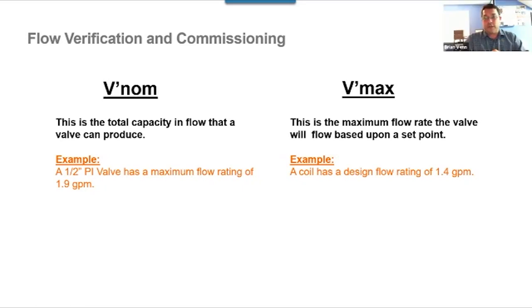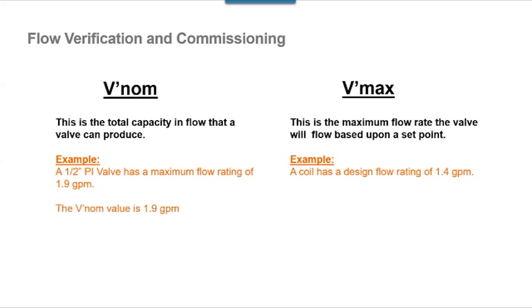And Bob, if I could on this one, this is also leading into the tie between kind of comparing this to a VAV, right? With a min and a max reading and a full open reading, but having the ability to change a factor or an orifice and actually control in the field the readings that you're getting. Yes. And I have a couple of slides coming up. We're going to talk about how to adjust that, but I always like to say, it doesn't take us as long to adjust the settings as it does to get the ladder and get up to the product itself. You know, always one of those situations.